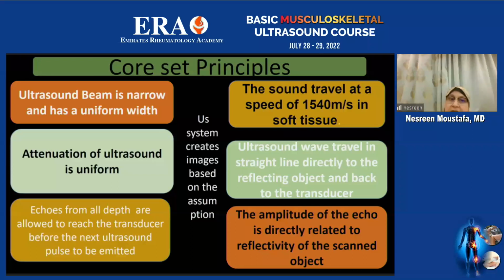The first one is that the ultrasound beam is narrow and has only a uniform width, which is not the case, and we will discuss it in the coming slides. The second one is that attenuation of ultrasound is uniform, meaning it's all over the tissues, irrespective of the tissue type, with the same reduction of intensity of ultrasound waves. The third one is that echoes from all depths are allowed to reach the transducer before the next ultrasound pulse is emitted, which is not the case.